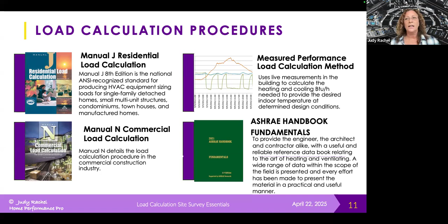The whole goal of the load calculation procedure is getting the numbers of how much energy needs to be added or removed from the space, information necessary for selecting appropriately sized space conditioning equipment. You go through the procedure figuring out how much resistance to all the different forms of heat transfer through a building is happening, how quickly it's happening, and therefore how much heat you need to add or remove from the space.